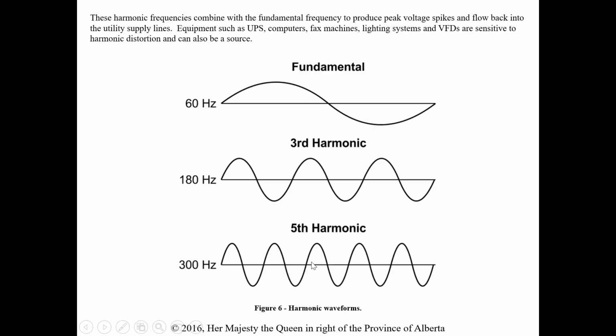actually rated for. So they'll put line reactors on the load and line side to help reduce those. So we want to protect the utility and protect our load. So we'll try and reduce those. These harmonic frequencies combine with the fundamental frequency to produce peak voltage spikes and flow back into the utility supply lines. Equipment such as UPS, computers, fax machines, lighting systems, and VFDs are sensitive to harmonic distortion and can also be a source. So we have our fundamental frequency. Again, our third harmonic is literally 3 times that. Fifth harmonic would be 5 times that.